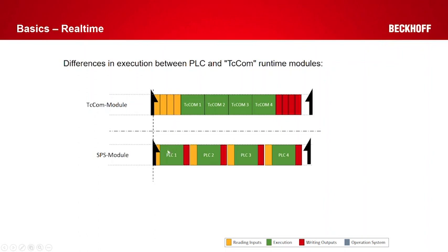This means if you would like to communicate from PLC 1 to PLC 2 via mapping, then the input update of the second PLC takes care of the mapping and copying all the information. And this means that PLC 2 has directly the last values from the same cycle. In the other direction, of course, one cycle is lost because then this input update is grabbing the information at the start of the next cycle.